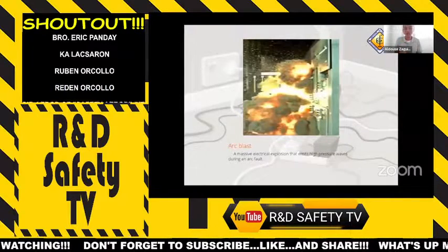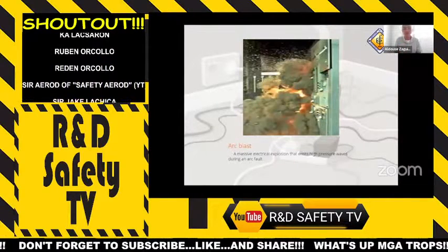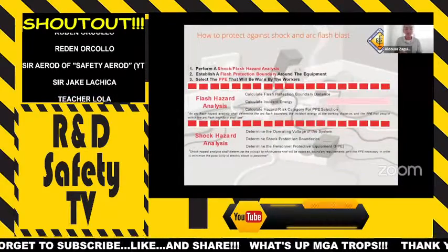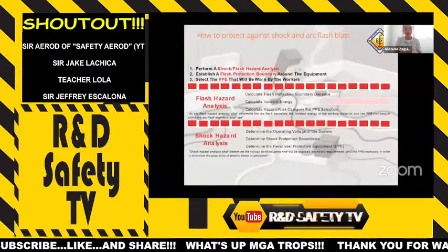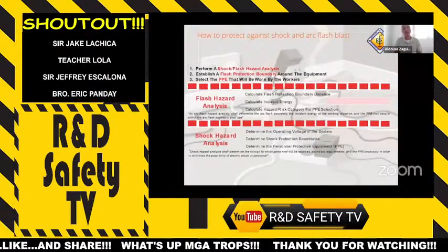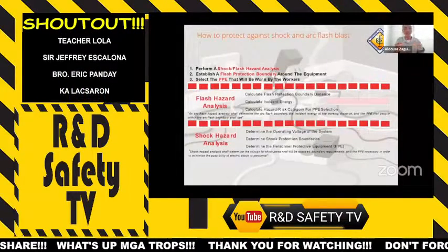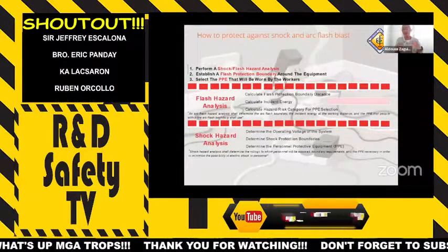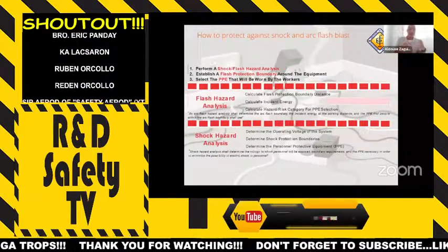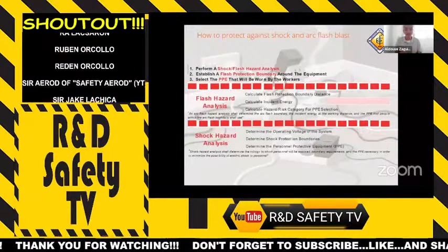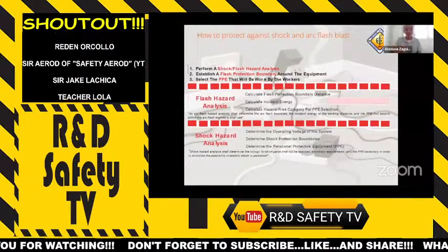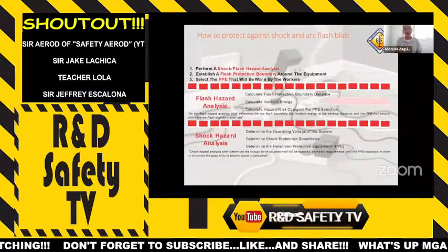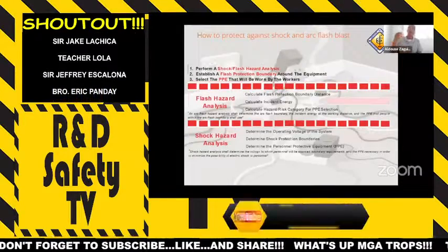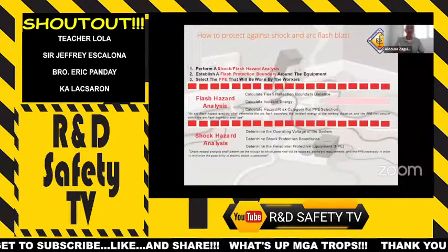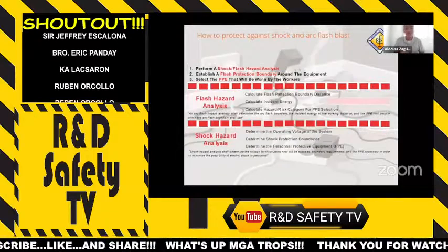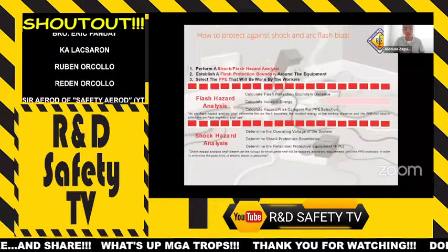So with this, how do you now protect your personnel against shock and arc flash blast? You start with engineering analysis — analyze the shock hazard and flash hazard, calculate the short circuit current, calculate the incident energy, and define the boundary around the equipment. With your incident energy calculation, it will also define what PPE is appropriate for the person.